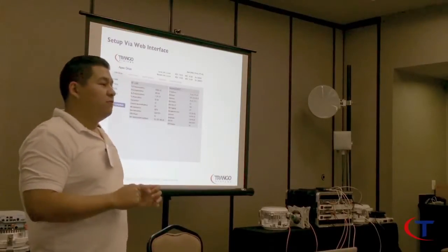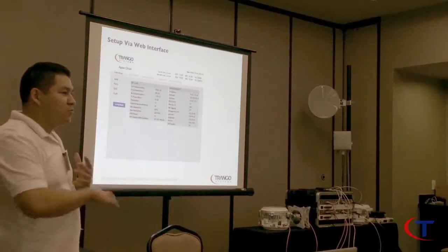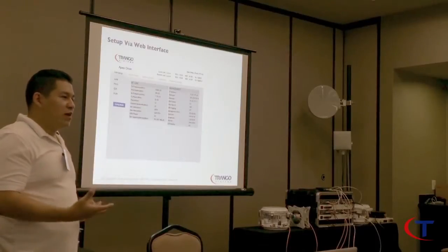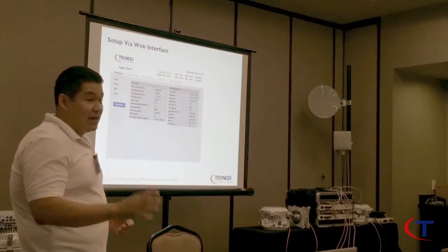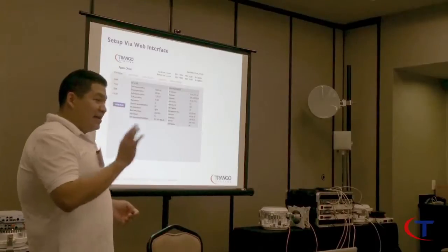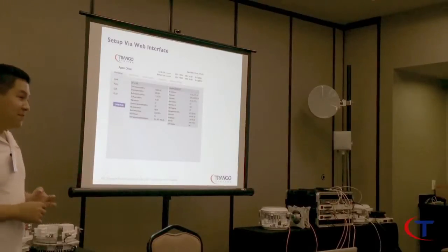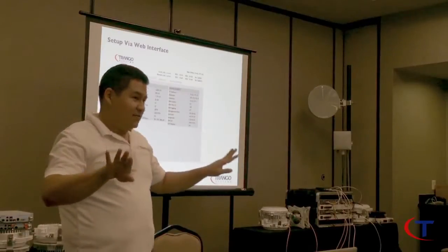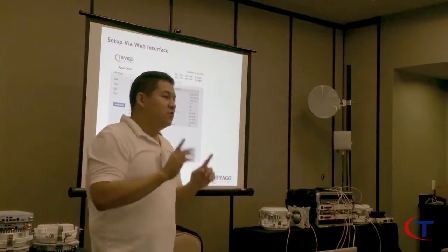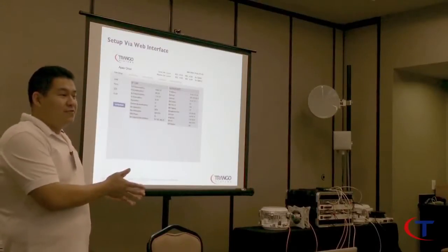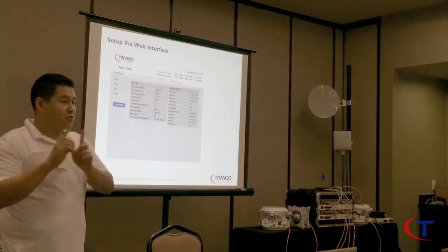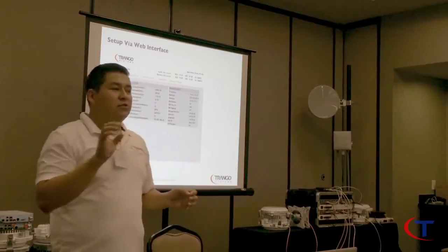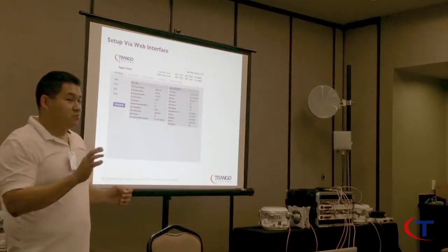The web interface is good if you want to go in and check something, just a brief overview, okay? And if you have somebody in the field that doesn't know what to do on the radio, only give them the view passwords, okay? Speaking of passwords, something that happens: the web interface and the CLI are different as far as password goes. If you change the password on the web interface, the default password is still on the CLI. They're different interfaces, so if you change one, the other one is still factory default. Okay, you have to change both.